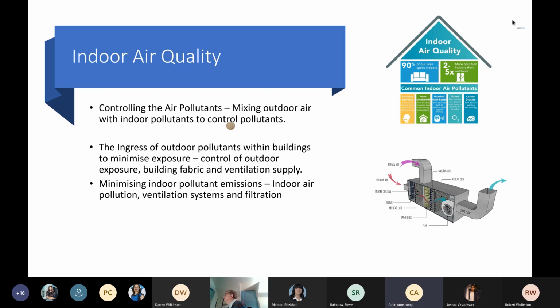It's used to physically remove particles, and in some cases, environmental gaseous pollutants from the ventilation air supply. Virtually all mechanical ventilation systems incorporate some form of filtration, but this is usually primarily just to protect the HVAC system rather than to improve the air quality. It's so that it doesn't damage the HVAC and it works to its full capacity and its design. It's not usually, as it says, for the quality, it's more for the system.